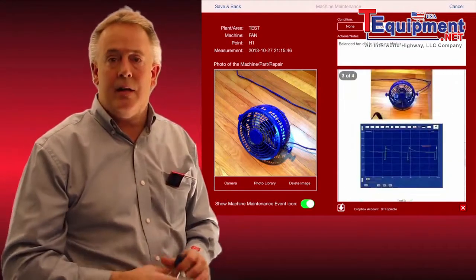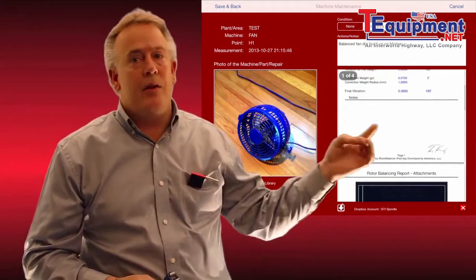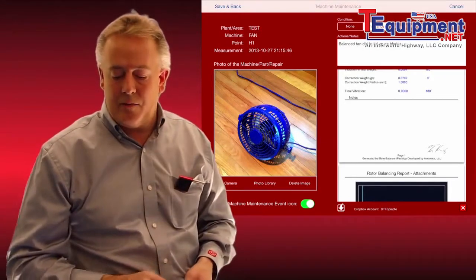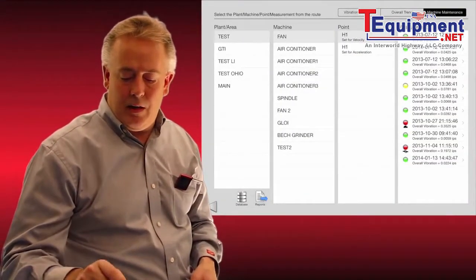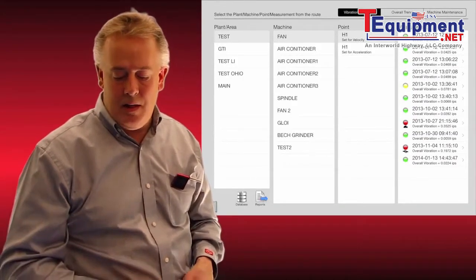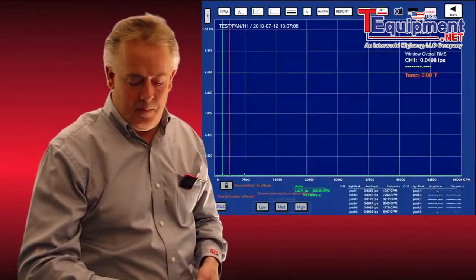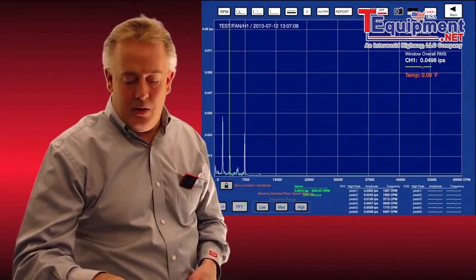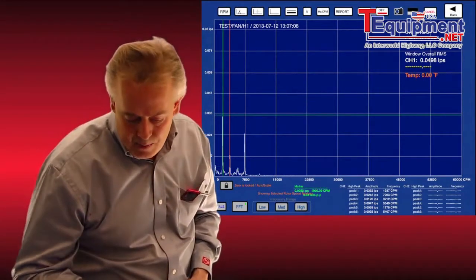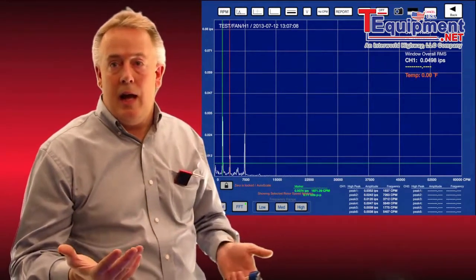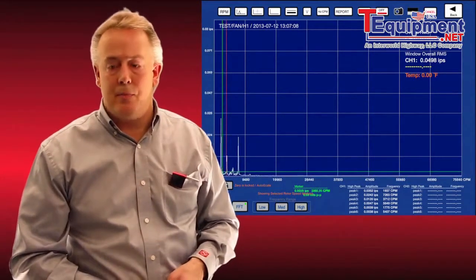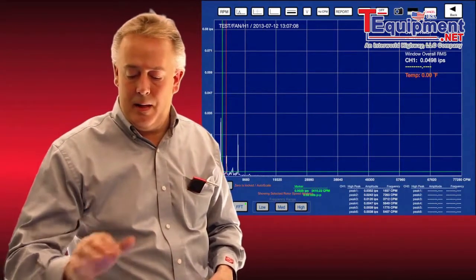This keeps track of everything — not only your measurements but anything you correct along the way. Moving back, we can look at any one of those spectrums and post-process them. We'll pull up a spectrum, bring it to scale, and with my cursor I can move it around, place it on a particular point, and see that measurement point's amplitude and frequency. I can pinch the spectrum in and out — all kinds of post-processing right from the iPad.